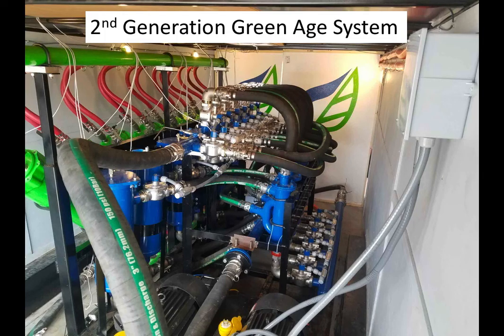So Idarado, since that first field trip, we've been working hard with Green Age. Green Age has been absolutely amazing, taking our advice as we collaborate. We've got a system now with, I believe, 136 sensors, so from 0 basically to 136. We have pressure transducers across the gradients of membranes. We have pressure sensors across our bags. We have continuous monitoring parameters for pH, conductivity, 5 different flow sensors.